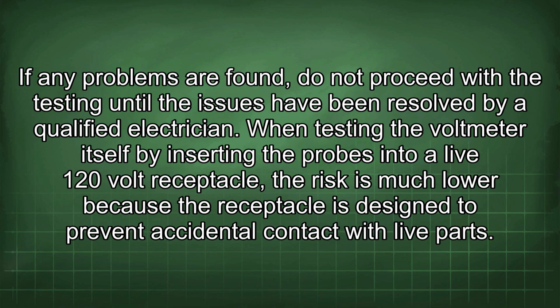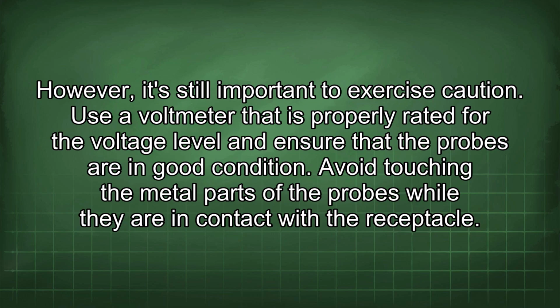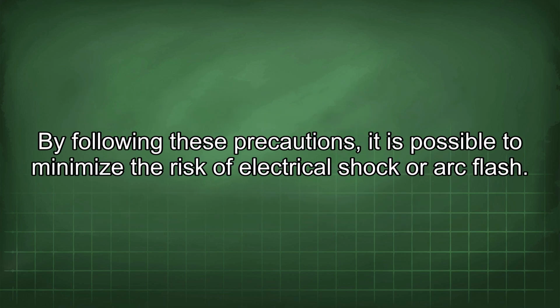When testing the voltmeter itself by inserting the probes into a live 120-volt receptacle, the risk is much lower because the receptacle is designed to prevent accidental contact with live parts. However, it's still important to exercise caution. Use a voltmeter that is properly rated for the voltage level and ensure that the probes are in good condition. Avoid touching the metal parts of the probes while they are in contact with the receptacle. By following these precautions, it is possible to minimize the risk of electrical shock or arc flash.